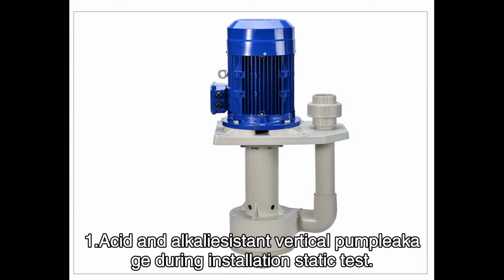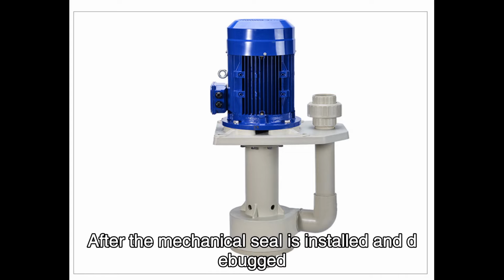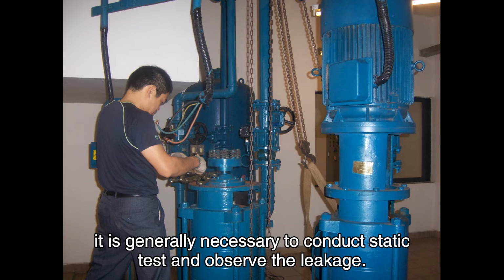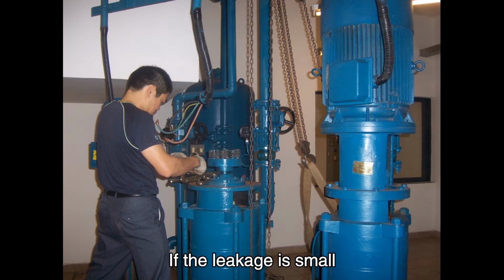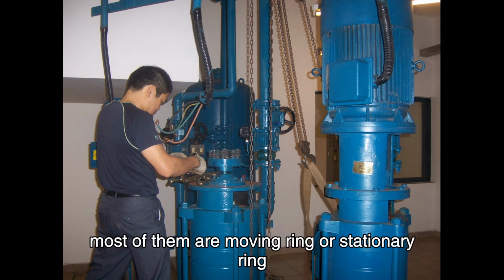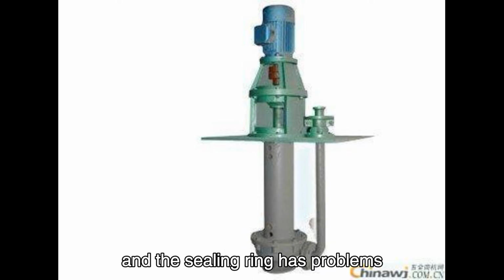During installation static test, after the mechanical seal is installed and debugged, it is generally necessary to conduct a static test and observe the leakage. If the leakage is small, most of the time the moving ring or stationary ring, or the sealing ring, has problems.